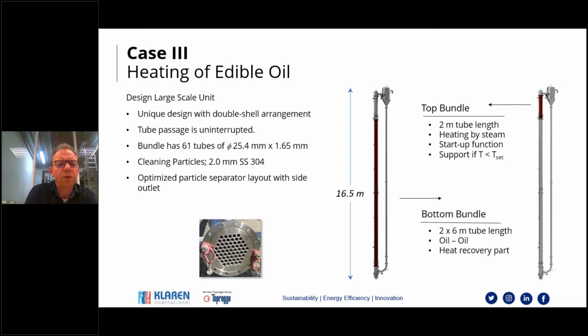It's not a very big bundle, so we only talk about 61 tubes. For the large evaporator, we go up to 1,000 tubes, so 61 is still a reasonable amount. So only 61 tubes with a diameter of 1 inch. But the total length has become 16.5 meters, so that's rather unique. It does give a stable system operation.